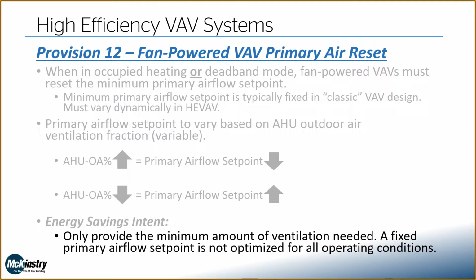The intent here: only provide the minimum amount of ventilation needed. A fixed primary airflow minimum set point is not optimized for all operating conditions. There are many times where we can reset that primary airflow set point and have a more efficient system than standard VAV.